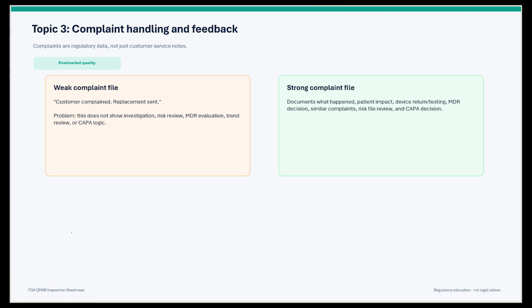or CAPA logic. A stronger complaint file documents what happened, whether there was patient impact, whether the device was returned or tested, what MDR decision was made, whether similar complaints exist, whether the risk file was reviewed, and whether CAPA was needed. Let us use the example of a hospital reporting that an infusion pump stopped during patient use. A QMSR ready complaint process would evaluate whether there was a device malfunction, whether a patient was harmed, whether the issue is repeating, whether FDA reporting is required, whether the risk assessment should change, and whether corrective action is needed.